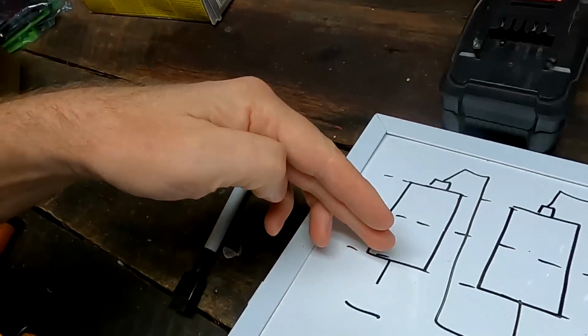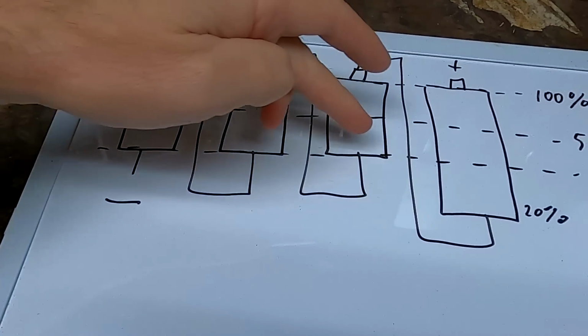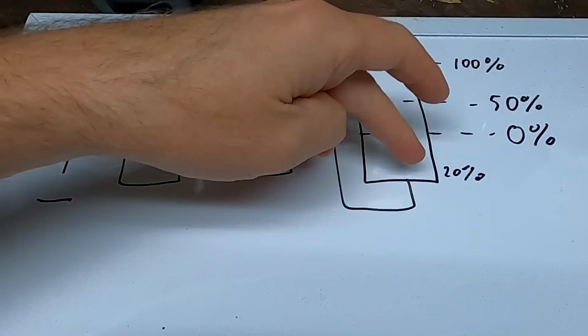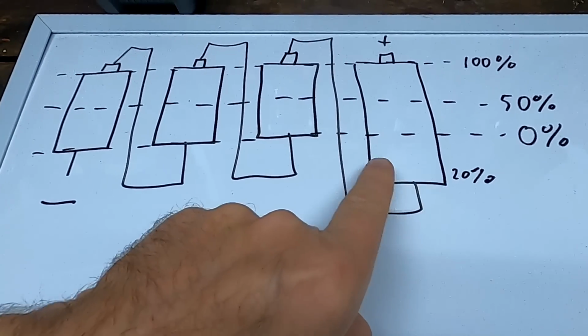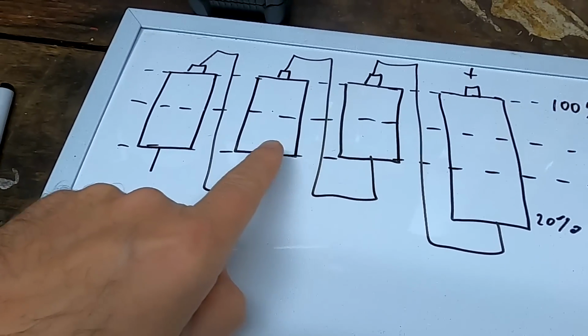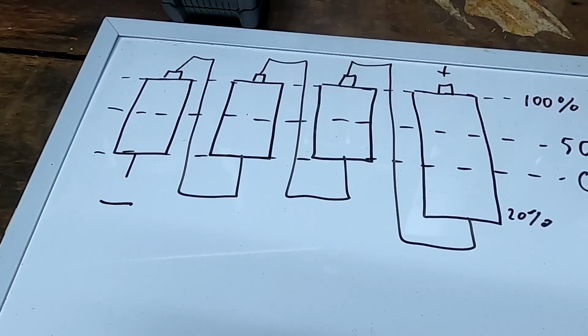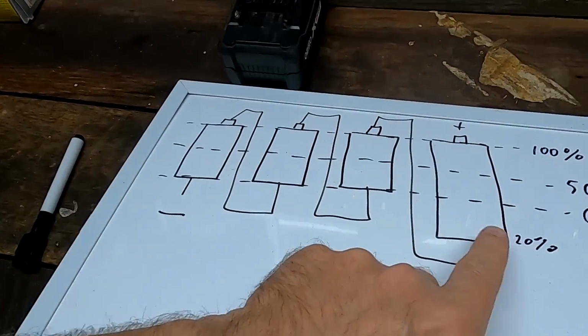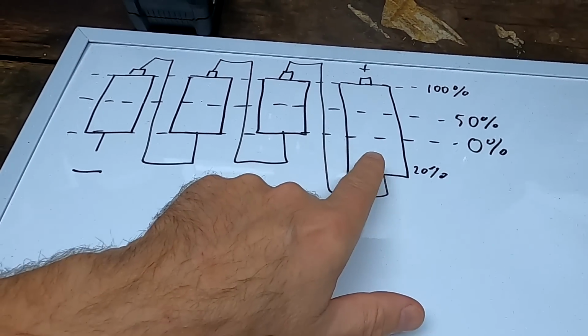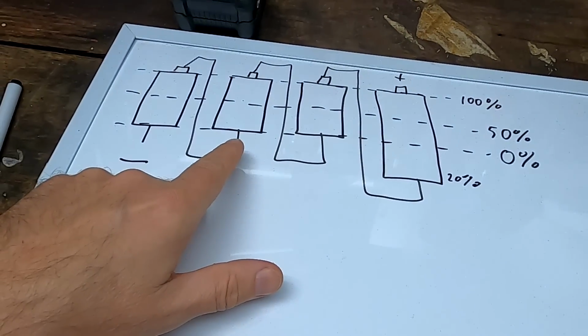Well, you could now argue, if we reach 0% state of charge with these 3 batteries and this one still has 20% left, why not get this energy out and into these batteries with a balancer? Yes, we could let the balancer run all the time, and it would technically take away some energy from these 304 ampere hour batteries and put this into the 280 ampere hour battery, and we could get the battery to run a little bit longer than without this balancing.